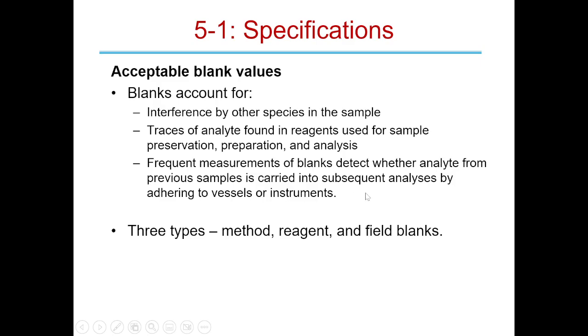Frequent measurements of blanks detects whether analytes from previous samples are carried into subsequent analysis by adhering to vessels or instruments. Big problem. This is actually the reason that you typically want to go from low concentrations to high concentrations, by the way. Because if you go from high, some of the concentration can be left over.